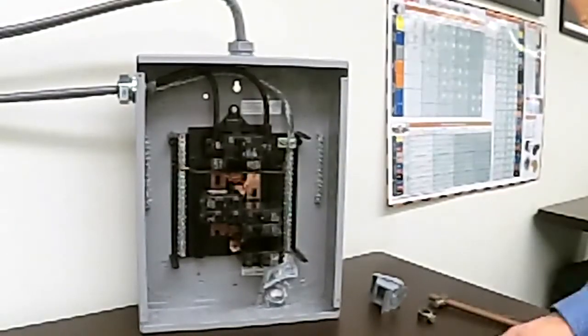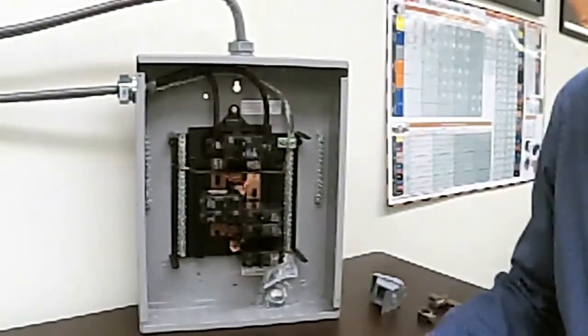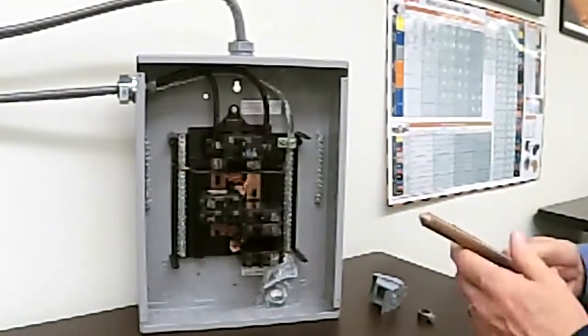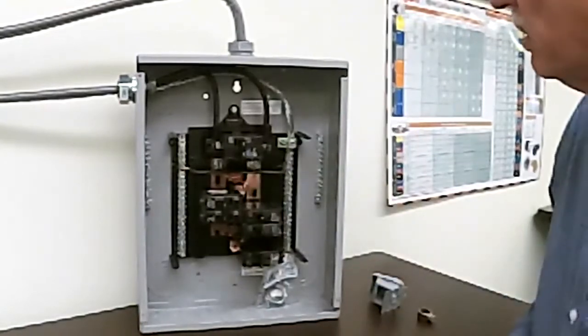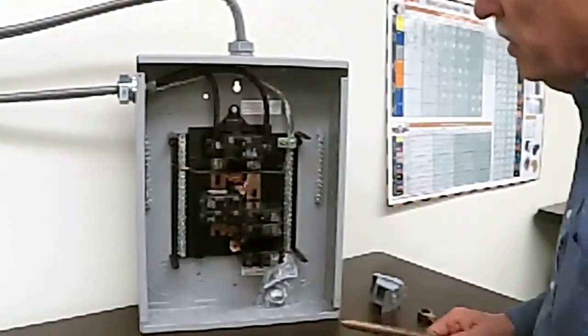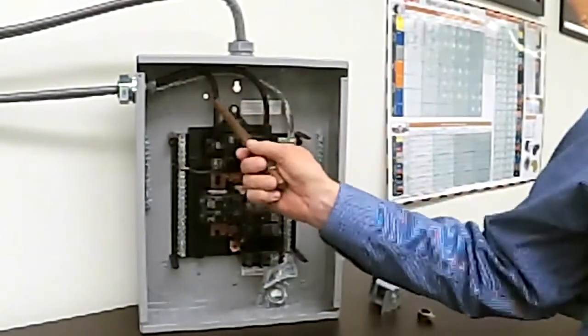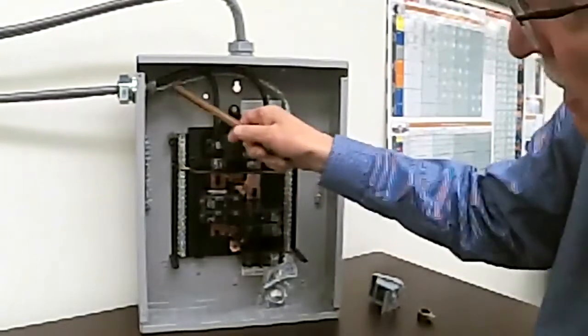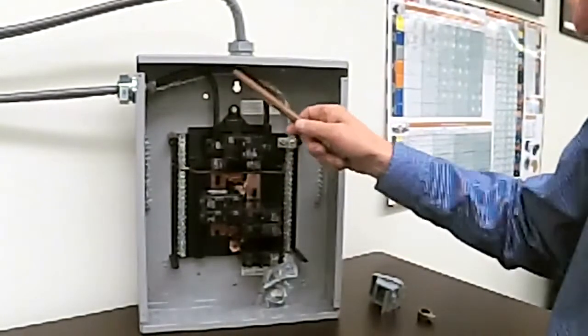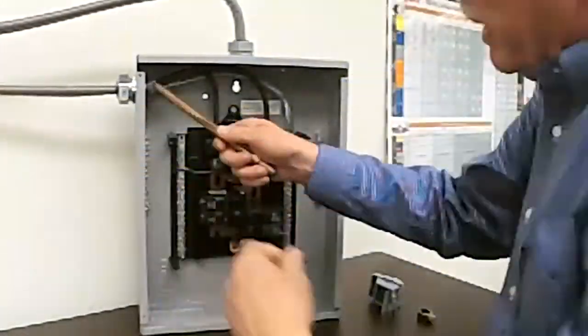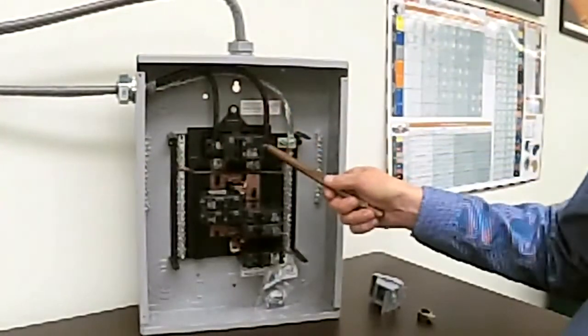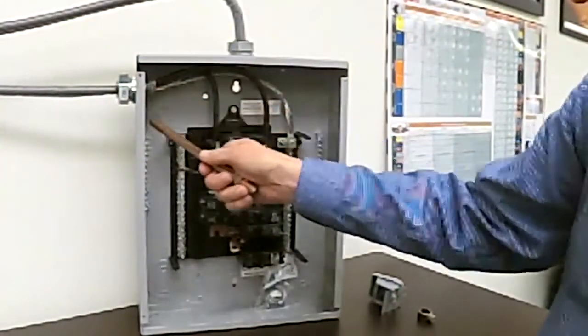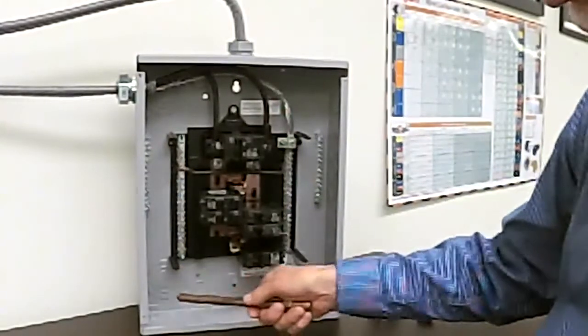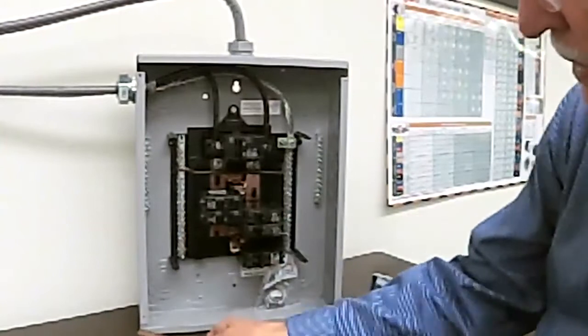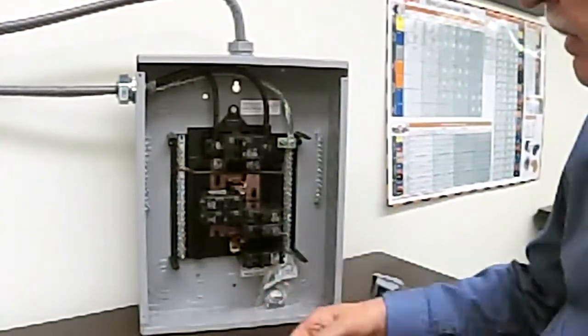Okay, in this panel, I'll use my ground rod as a handy pointer. We have a couple issues going on here. First of all, when you come in with your service conductors, you can see that I have them aimed upwards so that if there's any condensation that comes in by way of this cable, it's not going to make it over to the terminals on the main breaker. It's going to drip down here in the gutter space. And then there's holes in the bottom of this panel. There's spaces at the two front corners where water can make its way out.